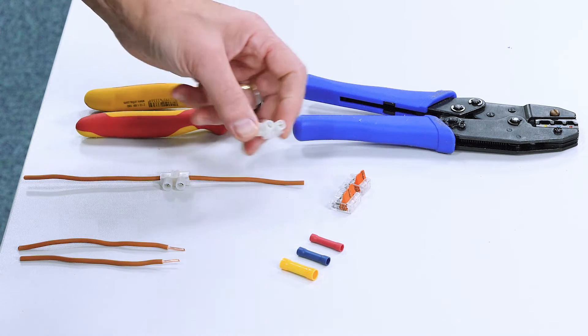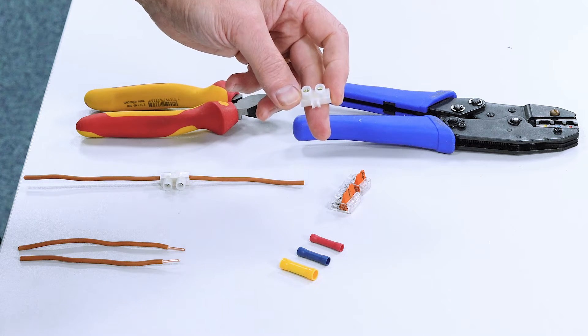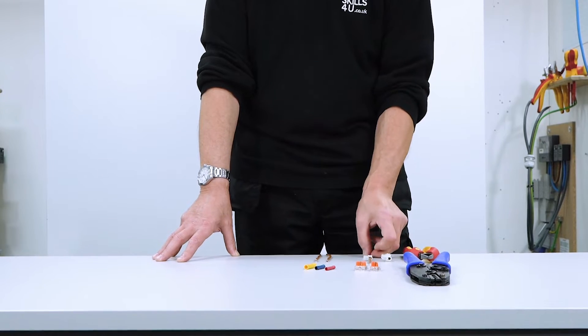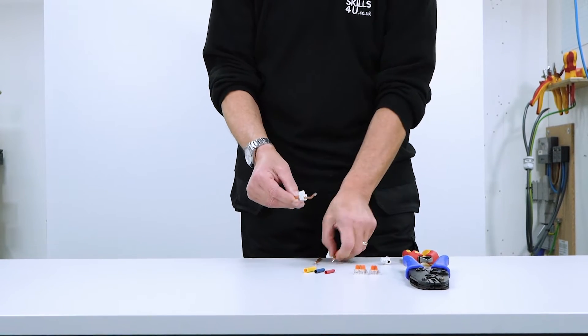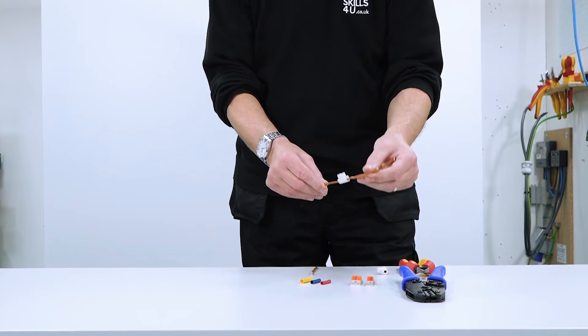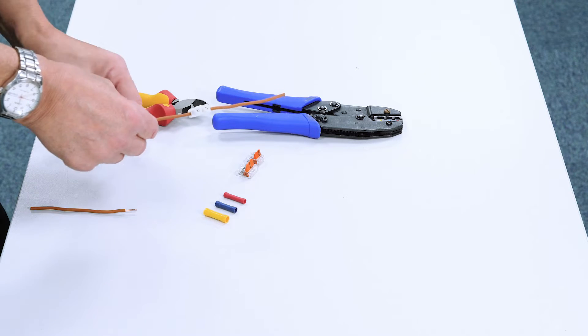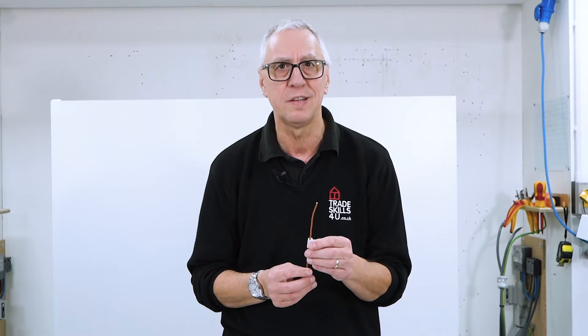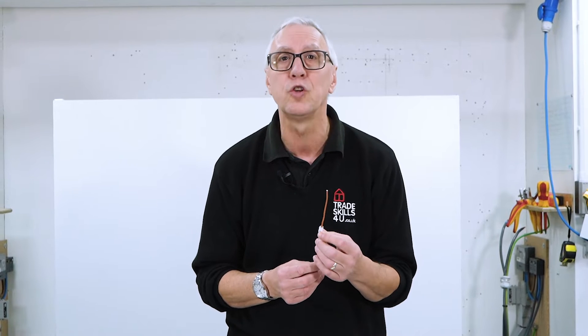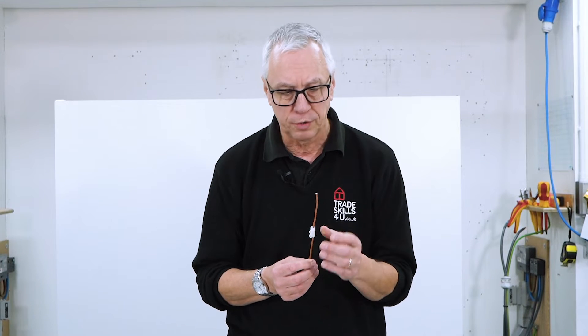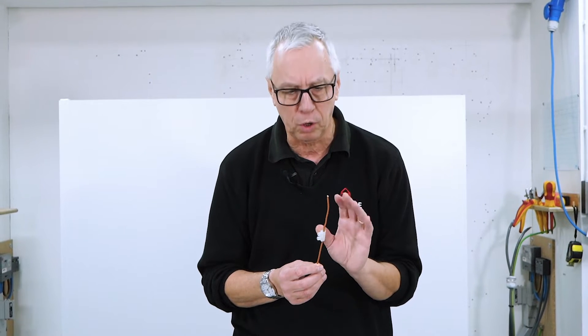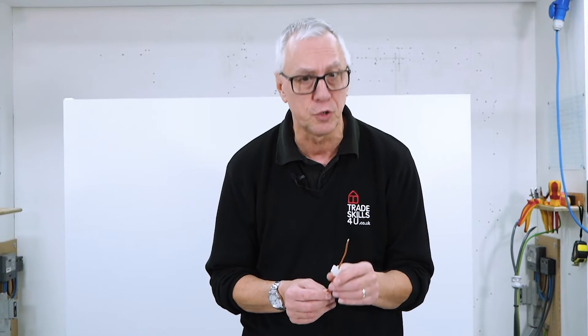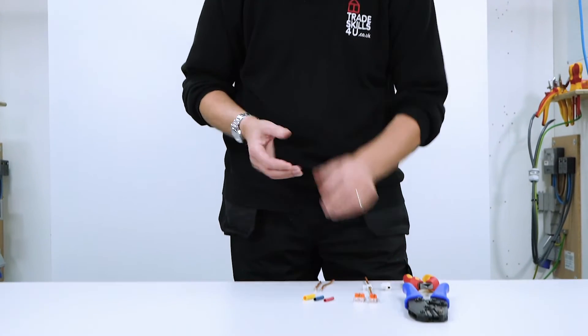Well, we have connector blocks and you've probably seen these around, they're very common. And I've just prepared one earlier there so you can just trim your conductors down and they just fasten in and screw down there. Now the problem with these is that they must always be in an enclosure. I've seen these buried in a wall before today, which isn't ideal because screw terminals can come loose. So never bury these in a wall, always make sure that they're in an enclosure.